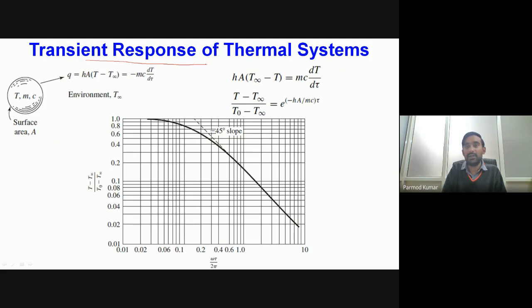So this is one very important parameter because of what happens if we are measuring temperature in some transient condition. What we have to do is make our thermocouple response fast in comparison to the change in the physical phenomenon. Okay, then only will we be able to measure temperature accurately. That is something which is controlled by the thermal inertia of the thermocouple.